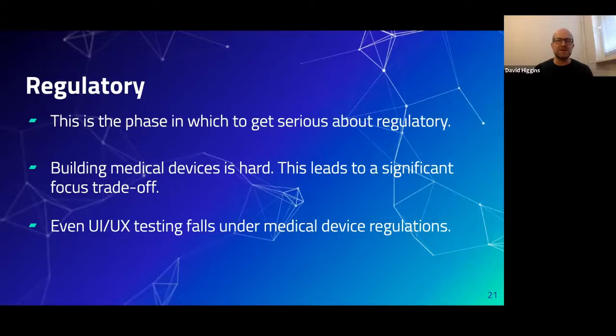Think of the case where you design your software for the ICU, with expert doctors in mind, and you test it on them. Don't forget that nurses also work in the ICU. What will they understand from the interface that is different from what the doctor understands? There's been a long history in medicine of people of different categories in the hierarchy switching off alarms because it kept beeping all night and they didn't know what to do with it. This is something you have to bear in mind with your software and design it early in the process, because it will be part of the regulatory bundle.